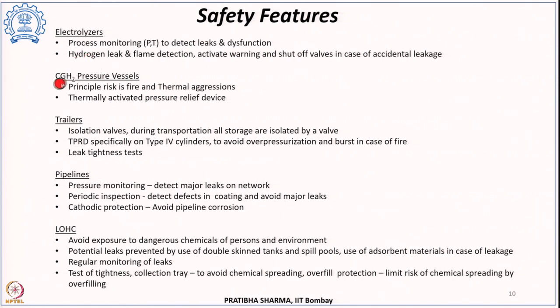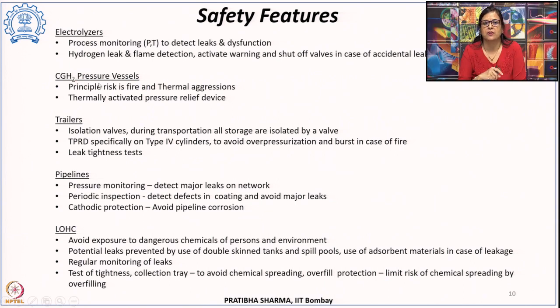In compressed gaseous hydrogen pressure vessels, the principal risk comes from fire and thermal aggressions. Thus, these pressure vessels are well equipped with thermally activated pressure relief devices, so that in unprecedented situations, that pressure relief device could release the excess pressure which is being created inside the vessel. In the compressed gaseous hydrogen trailers which carry these pressure vessels, there will be isolation valves present. Now, these isolation valves are such that each tank is isolated and has an individual or independent valve.